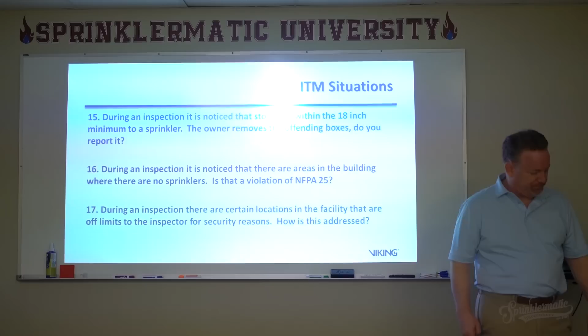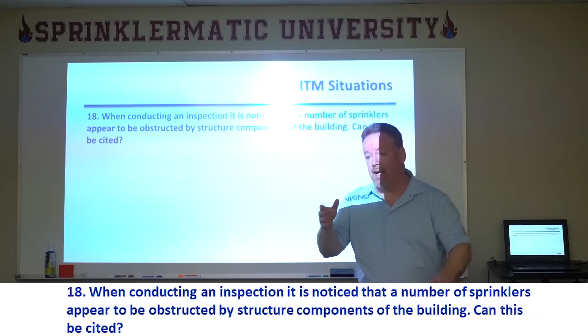Another ITM situation: when conducting an inspection, it's noticed that a number of sprinklers appear to be obstructed by structural components of the building. Can this be cited? Remember yesterday we talked about the three times rule and the beam rule regarding obstructions to spray patterns. In this case, I'm walking along and I come across a sprinkler with a beam right next to it. It's a false beam, obviously put in later to create a nice rustic look. Or it could be ductwork, or anything, right there next to my sprinkler.